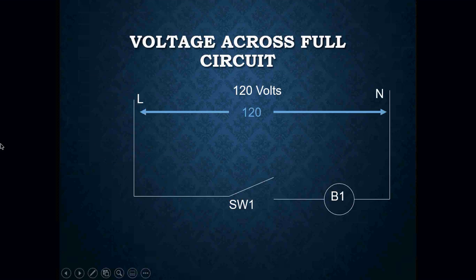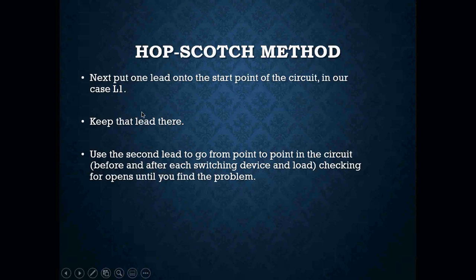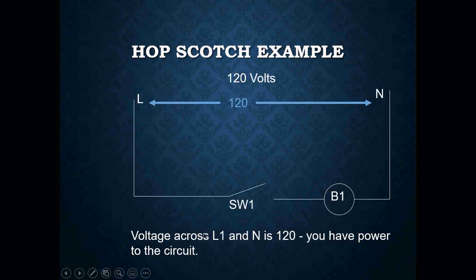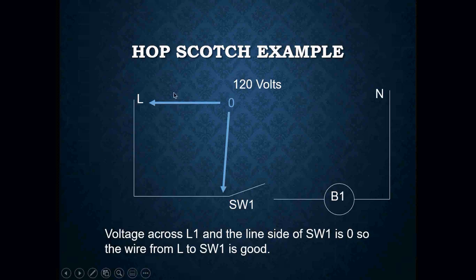You are then going to leave one lead at the beginning of the circuit, usually on your black wire, your line 1, and hopscotch your way through the circuit. So here we are. Voltage across L1 and neutral is 120 volts. We have power to that circuit. Again, leaving one lead at the beginning of the circuit, you are now going to take your other lead and just simply move your way down the circuit. So in this case, we are reading 0 volts between the beginning of the circuit and our switch. We are reading 0 volts here because we are reading nothing more than a wire from point A to point B. There is no difference in potential there. So we are going to read 0.